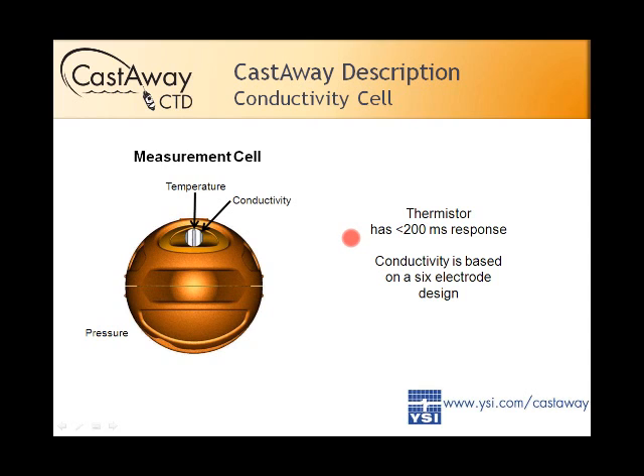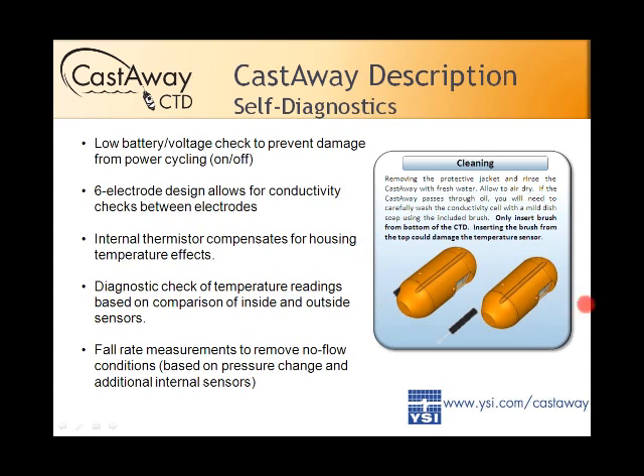The thermistor has a very fast response rate — better than 200 milliseconds — putting it right there with the competitive field as a state-of-the-art CTD. For cleaning the sensor, it is a flow-through design. There's a bottle brush included with the kit; if you get oil or some other contamination on the sensors, you can gently rub that bottle brush back and forth inside and use a little bit of soap and water.